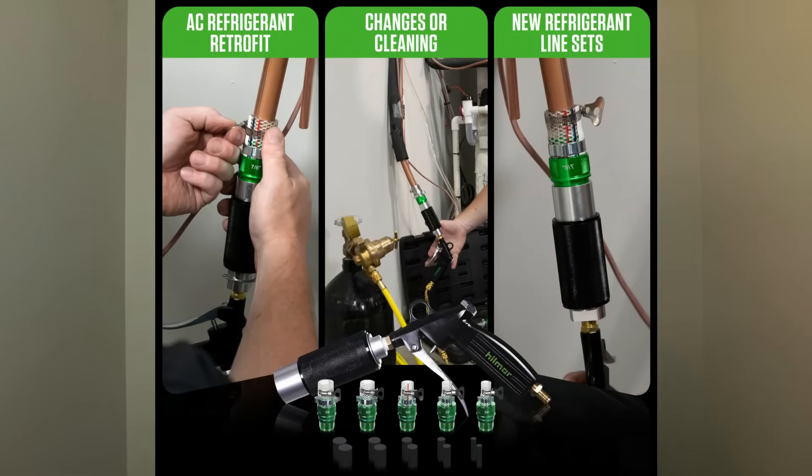There's a chance Daikin already had a solution based on their past experience with R32. Since R32 uses a different oil from R410A, these two refrigerants should never be mixed. Whenever you replace an AC system using R32, treat it like an old R22 system — there needs to be much more emphasis on cleaning out the line set. On top of a nitrogen flush, pulling a triple vacuum down to 500 microns, you also need to flush out the line set with RX11. If there's any gunk buildup, use a line set scrubber. These additional steps in the install process are not optional and can't be skipped.